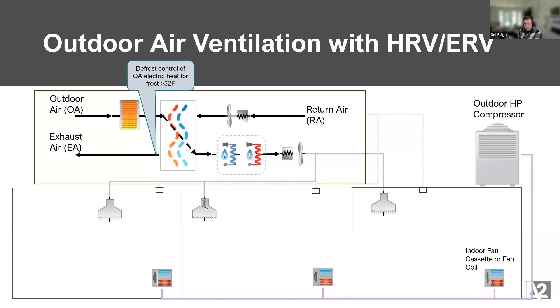This really happens when there's water in the building. If there's humidity in the air inside, you get frost risk on the outside, leaving that heat exchanger. I asked several manufacturers if they design for this, and they said no, the buildings are just really dry. That's perhaps true, though post-COVID we now understand humidity in the air is important to maintain, so some buildings may now have humidifiers.